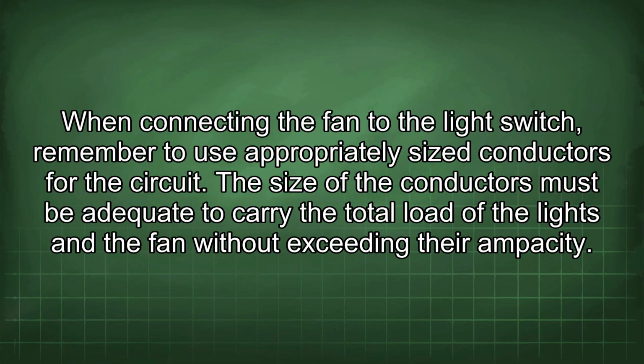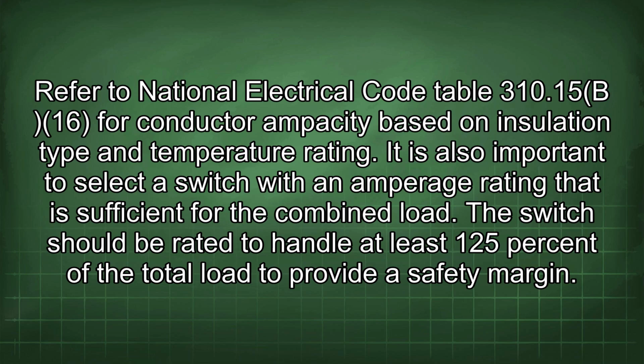When connecting the fan to the light switch, remember to use appropriately sized conductors for the circuit. The size of the conductors must be adequate to carry the total load of the lights and the fan without exceeding their ampacity. Refer to National Electrical Code Table 310.15(B)(16) for conductor ampacity based on insulation type and temperature rating. It is also important to select a switch with an amperage rating that is sufficient for the combined load. The switch should be rated to handle at least 125% of the total load to provide a safety margin.